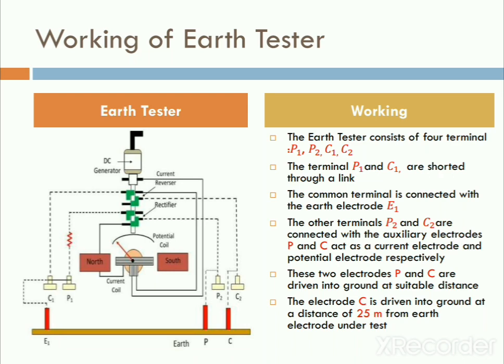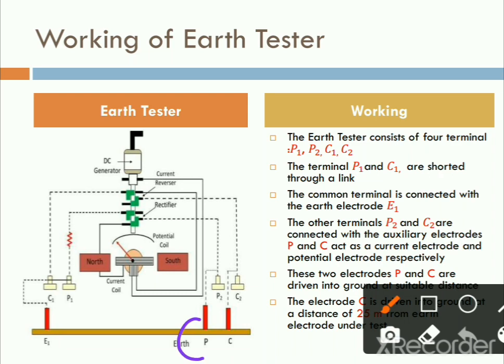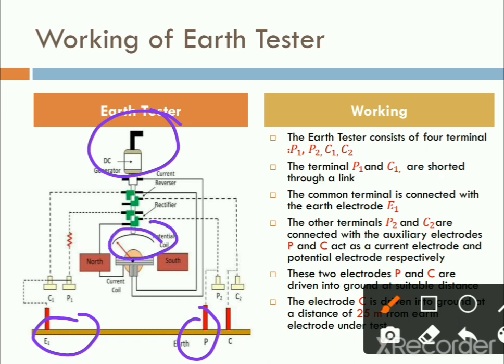Second point: again fix the electrode P at a distance of 3 to 4 meters near to the earth electrode and calculate the resistance. Fix P at 3-4 meters from the earth electrode, then start the DC generator by rotating the handle, and the resistance value can be read from the scale.